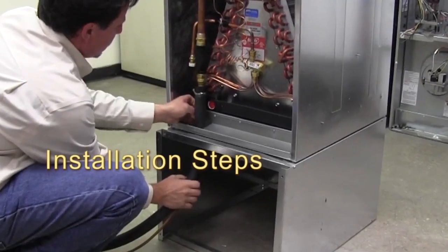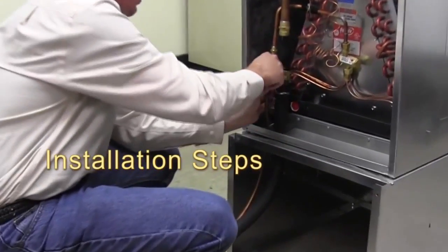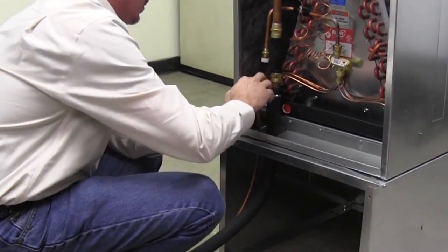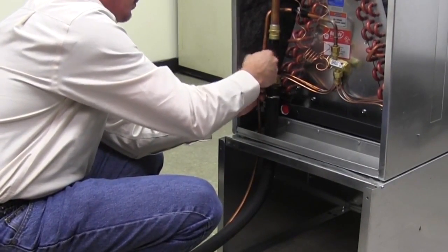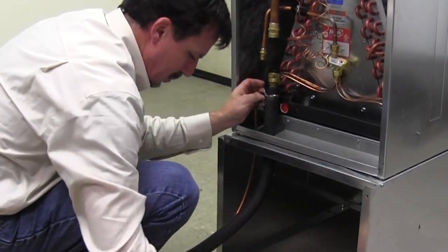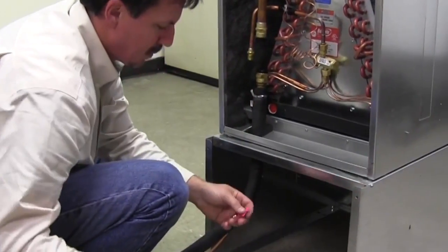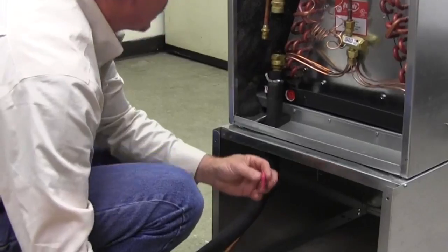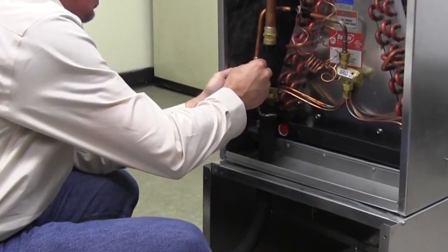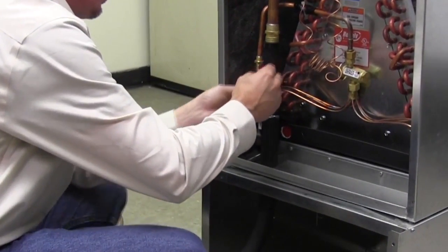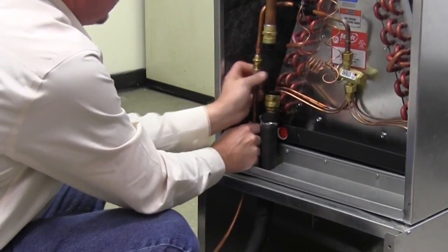With the proper indoor coil in place in the furnace, run the AccuCharge line sets up through the openings provided in the furnace and align with the fittings on the coil. Lubricate the threads and o-ring of the male fittings with the POE oil provided in the packet. Be sure to keep enough oil for the outdoor unit connections. Start the threads by hand with the liquid line first and then the suction line.